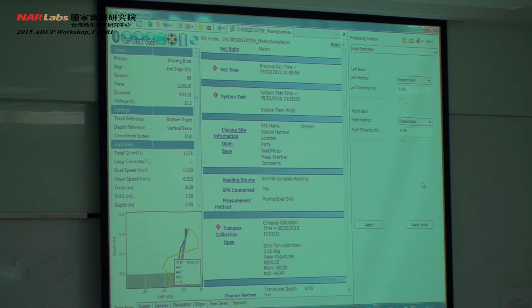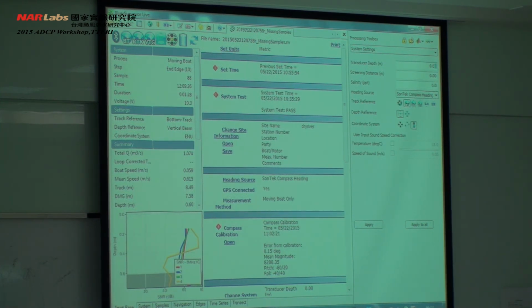Something else that we didn't do, we hadn't put in a transducer depth. So it was thinking that the transducer was directly at the water surface. I can just change that now. And instead of saying 1.077, by putting in an 8 centimetre transducer depth, it now says the total Q is 1.263. So it's quite a significant error that would have given us if we hadn't put that in.